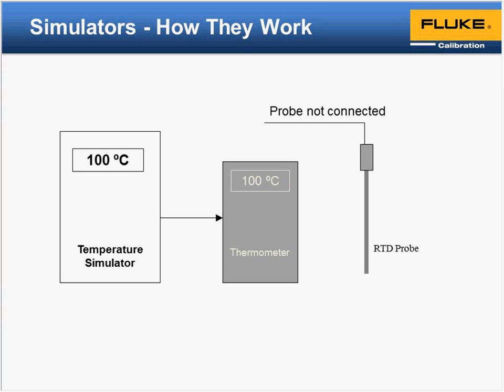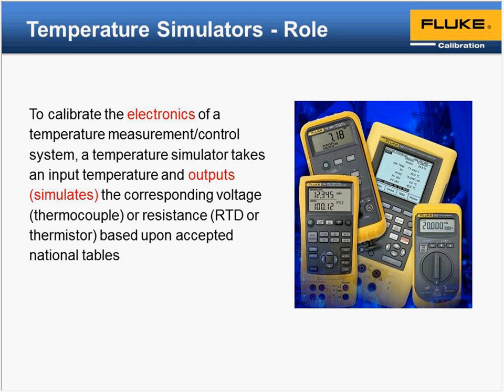We're going to see, okay, is this working with the specs we think it is, or is it out of tolerance? Calibrate, basically, the electronics. You're going to take the input, something we just discussed. Basically, we're simulating. In our case, where we're simulating an RTD probe, we're going to be working typically with a range of 100 ohms up to 138 ohms for our example here, because we are working with 0 to 100 C. So again, the nominal settings of a 100 ohm probe, typically 100.0, and 138.5 at the 100 point.